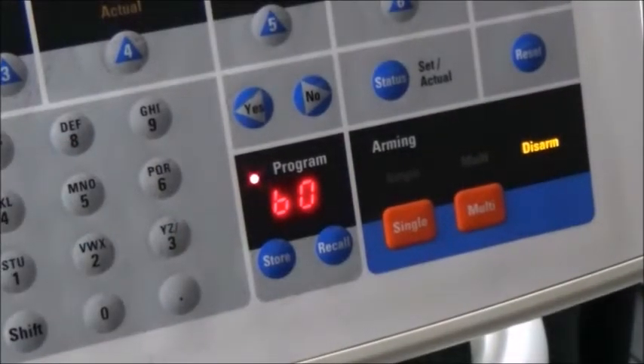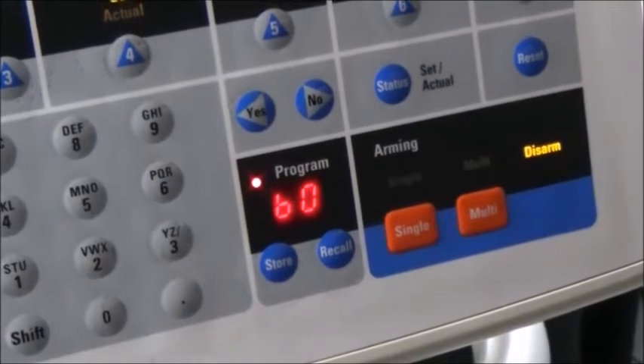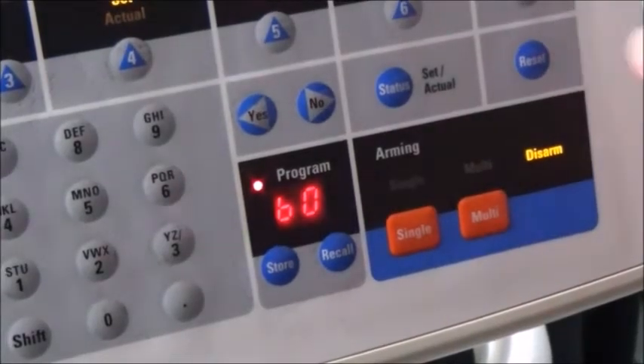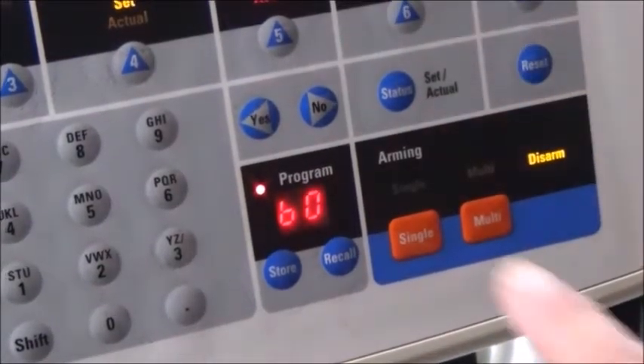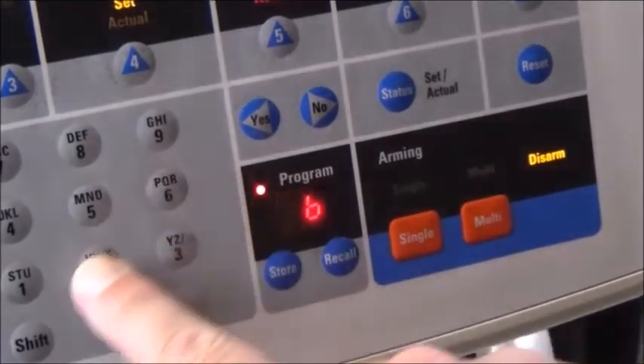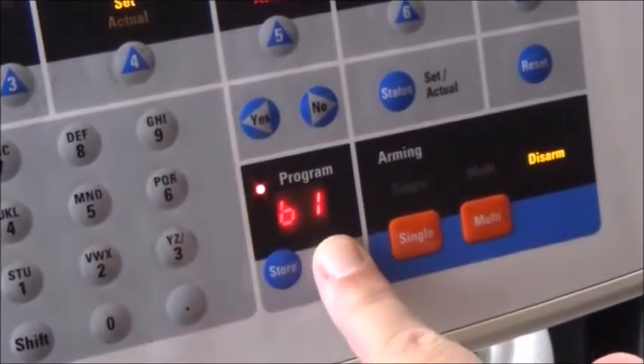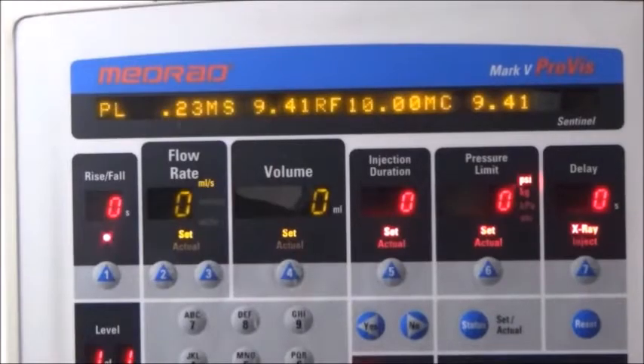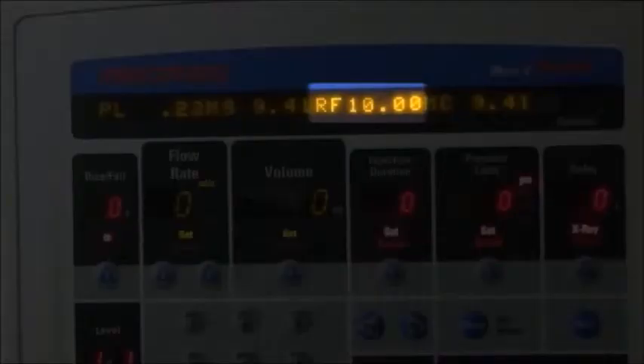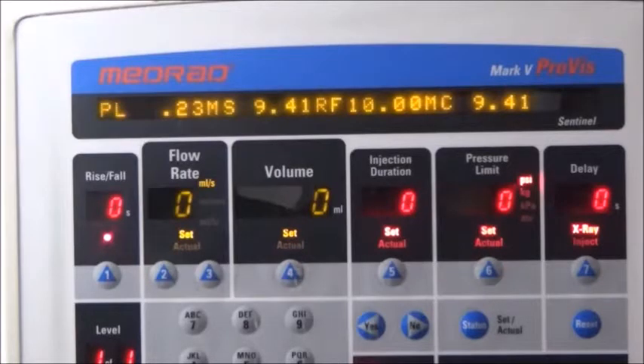In this step, we check the reference voltage for the plunger ram and mechanical stop positions. Press Reset, Recall, 61, Recall. This puts us in a special calibration mode. The number to the right of RF, which stands for reference, on the display is the current reference voltage. It should be 10.00 volts DC plus or minus 0.01.